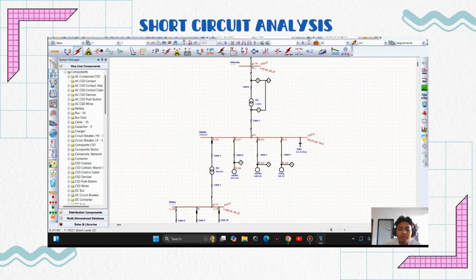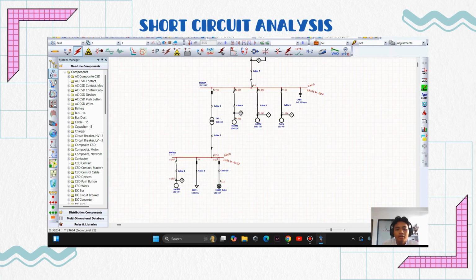Next we proceed to the MV bus. The MV bus has lower fault current than the others, not as aggressive as the SWGRA, because it reflects the sum of all downstream contributions reduced by the impedance from transformer 2 and the cables. So it is already reduced by the transformer, so the MV bus fault current is lower than the SWGRA. Next we will go to the graph.